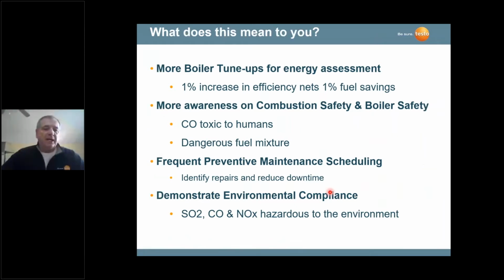So basically today, with energy prices going up, oil prices, the barrel of oil's going up today, a lot of things going on in the international markets, of course, boiler tune-ups and energy assessment are very important. We'll talk a little bit about energy efficiency, how that relates to fuel savings, that the combustion efficiency provided by your analyzer equals fuel savings. We'll talk about carbon monoxide in general, CO, how it's toxic to the operators or to the people in the building, and also the possibly dangerous fuel mixture you may have.